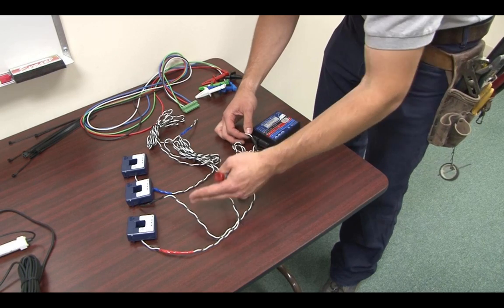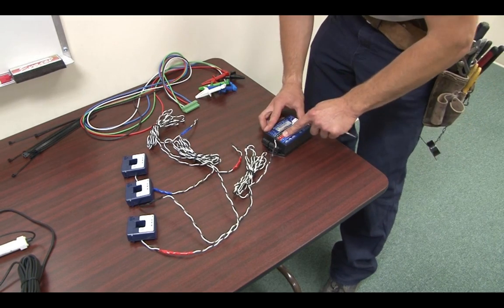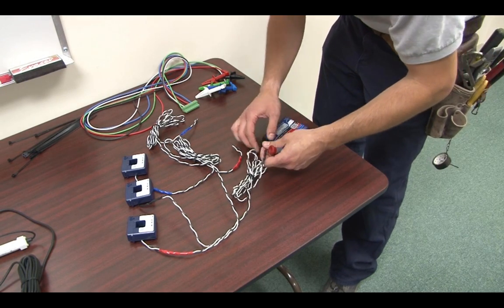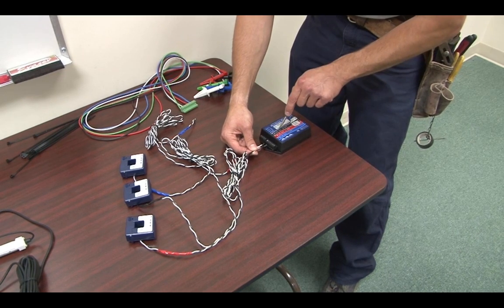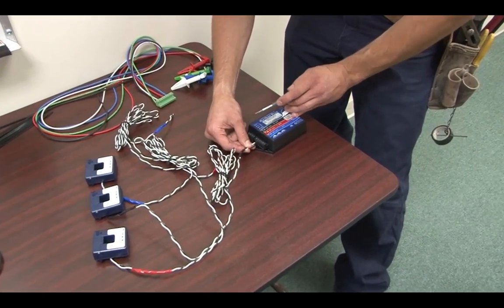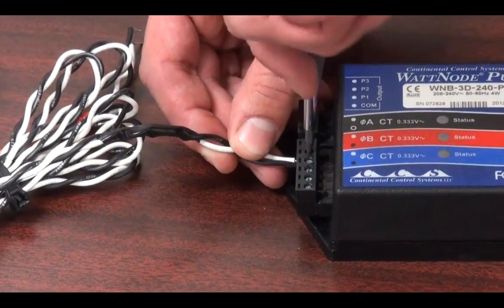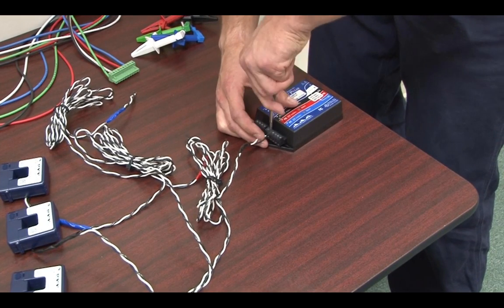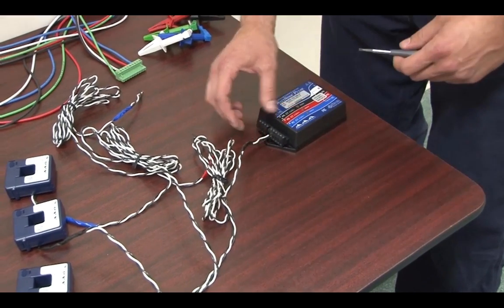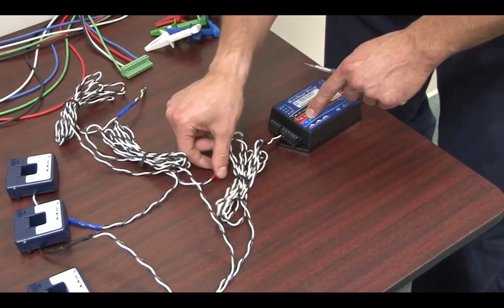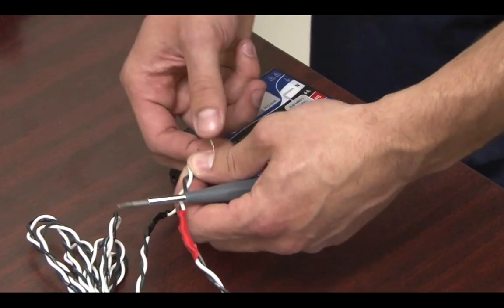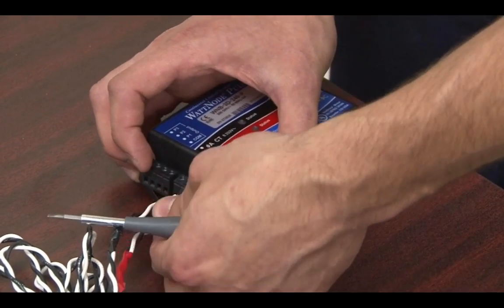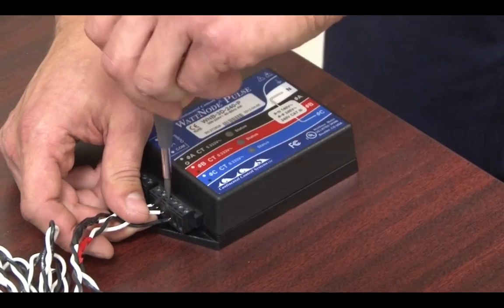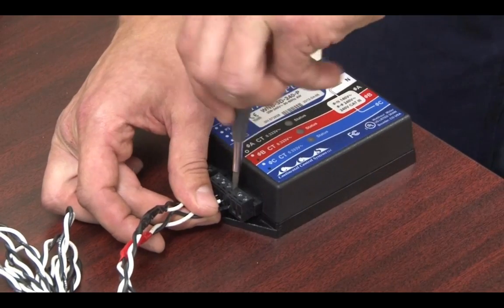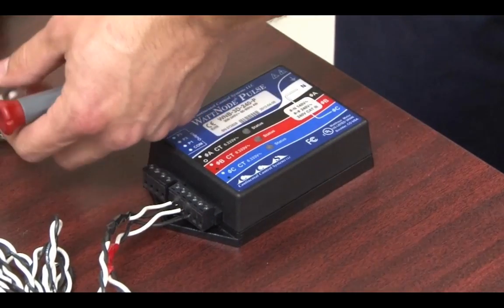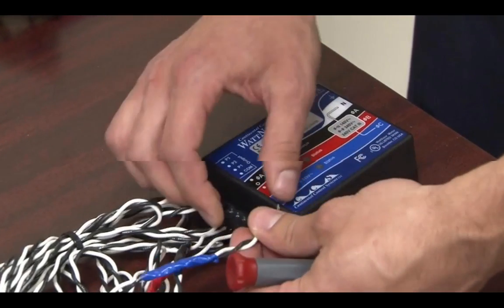I've also labeled the CTs black, red, and blue to represent the phase colors. These line up with the colors on the Wattnode as well as the colors in the electrical panel. We start out by wiring the black CT to the phase A terminal, to the white and black terminals. We'll then wire the red CT to our phase B terminal. Once again, the white wire will go on the white terminal and the black wire will go on the black terminal. And lastly, our phase C CT, the blue, will get wired to phase C of the Wattnode.